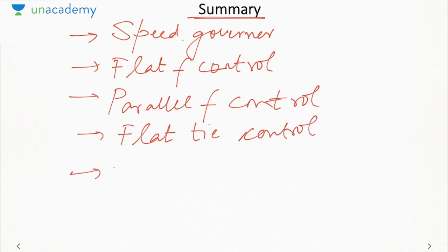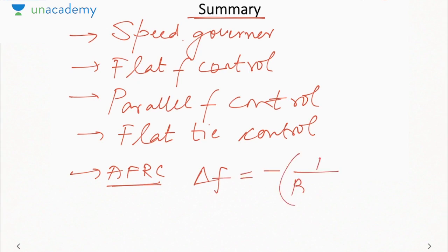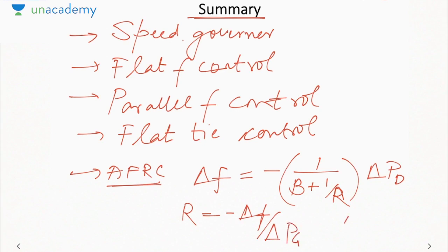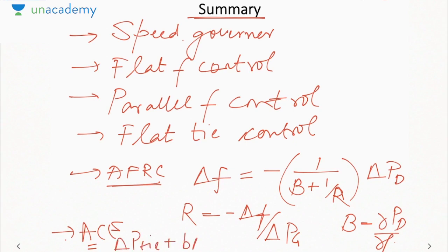Then we saw AFRC, which was given by delta F is equal to minus 1 by B plus 1 by R into delta PD. Okay, this was given as AFRC. Here R was minus delta F by delta PG, B was del PD by del F, and last we saw ACE, which is delta P tie line plus B delta F. B is called the frequency bias.